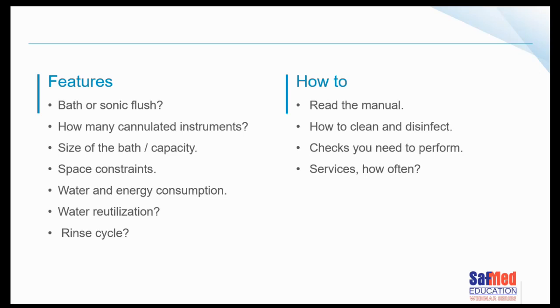You need to think about the size of the bath, the capacity of the bath. So, of course, the manual or the instruction or the guideline or the person who sells you the bath can tell you what its capacity is, what volume of instruments can it take, what weight of instruments can it take, how many lumen flushes does it have attached to it, can you put in one load at a time. You need to look at the size of the bath, the depth of the bath. Will it fit the length of the instrument? So some of the Da Vinci instrumentation, for example, doesn't fit in standard baths, and you may need a slightly bigger bath for that. What are the space constraints in the unit that I'm going to be putting it in?